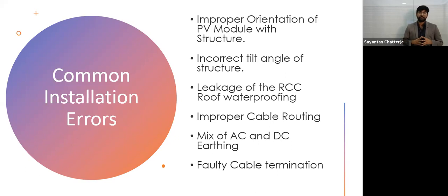Improper cable routing is a huge setback for the solar industry, especially in rooftop. We have to decide where to put the cable through the cable tray and where we should use conduit pipes, and in a conduit pipe, what the free space should be and how many cables there should be. Depending upon the current carrying capacity at the conduit level, we have to check the cable loss calculation. If we calculate the cable loss based on open air routing, and we put the cables in conduit without proper spacing, there's a huge loss, and that will affect the net energy fed into the grid.